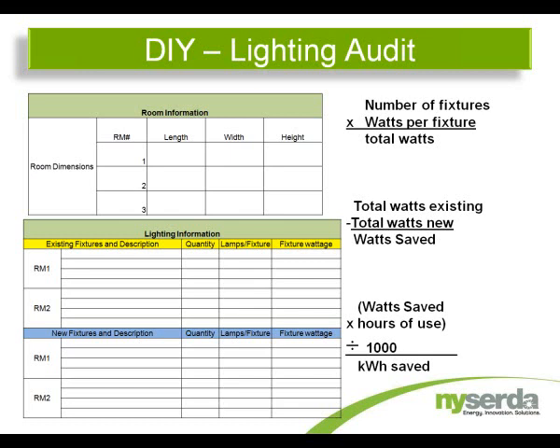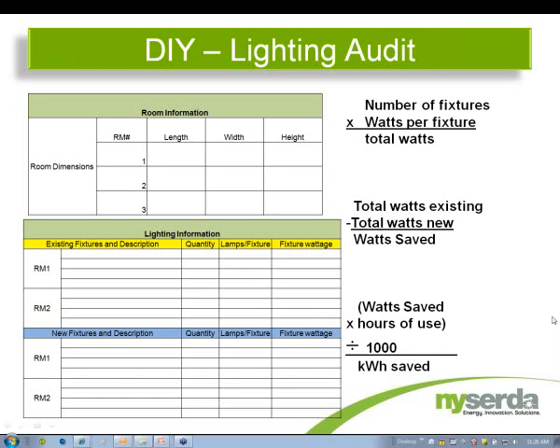What you really need to start off with is identifying your baseline - what's currently in your school. You need to identify your existing fixtures, the quantity, the lamps in the fixture, and the fixture wattage. Once you have that, you can multiply your number of fixtures by your watts per fixture, and that'll provide your total watts. Total watts existing less your total watts new will be your watts saved.